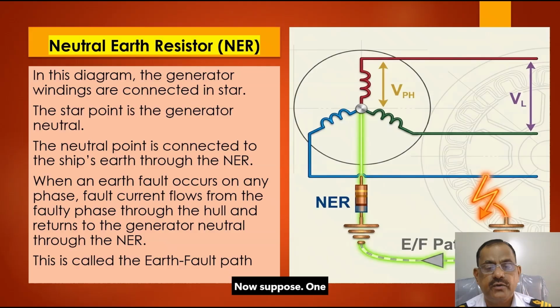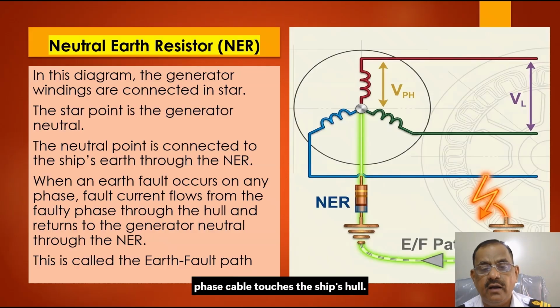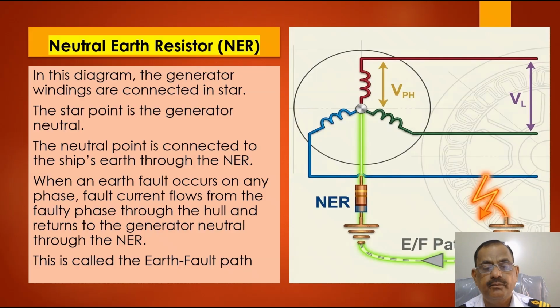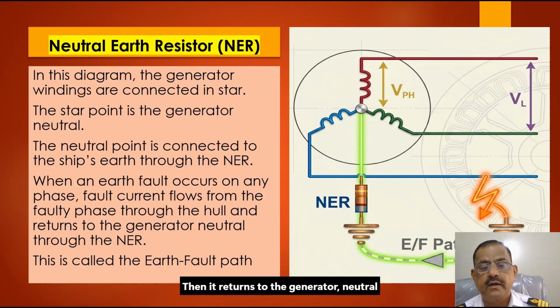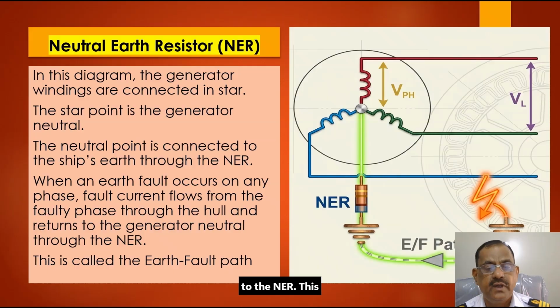Now, suppose one phase cable touches the ship's hull. The fault current flows from the faulty phase into the hull. Then it returns to the generator neutral through the NER. This complete route is called the earth fault path. The NER controls the amount of current flowing in the path.